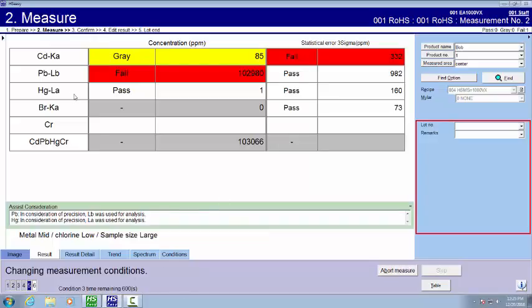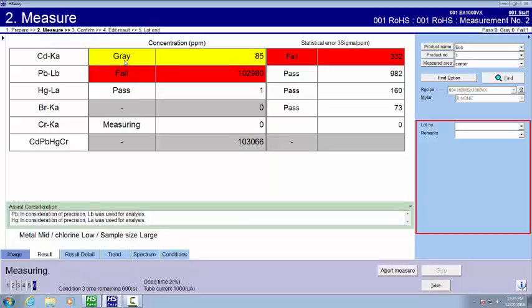You notice with cadmium it's a gray area. This is a good example. Gray area means we're uncertain if it's passed or failed. It's in the area of uncertainty of measurement. This particular sample would normally go be retested again, remeasured, or possibly go out for a destructive test. It's in the gray area where we cannot be positive based on the uncertainties that we've allowed to say pass or fail.